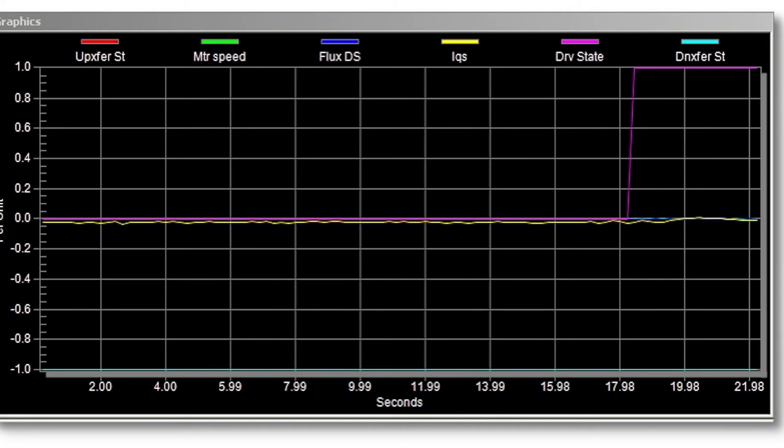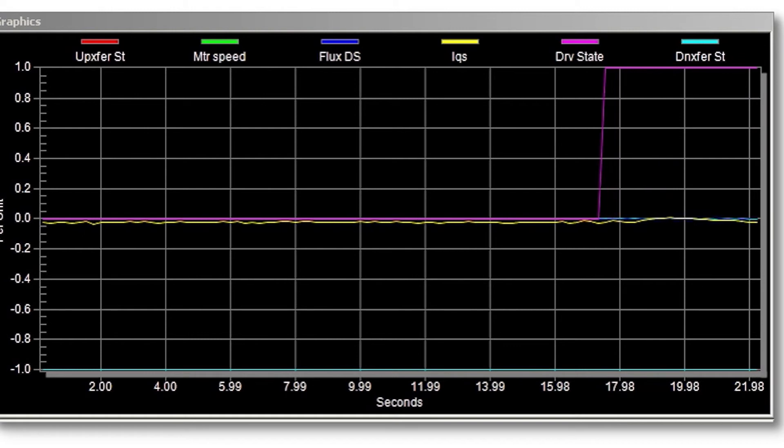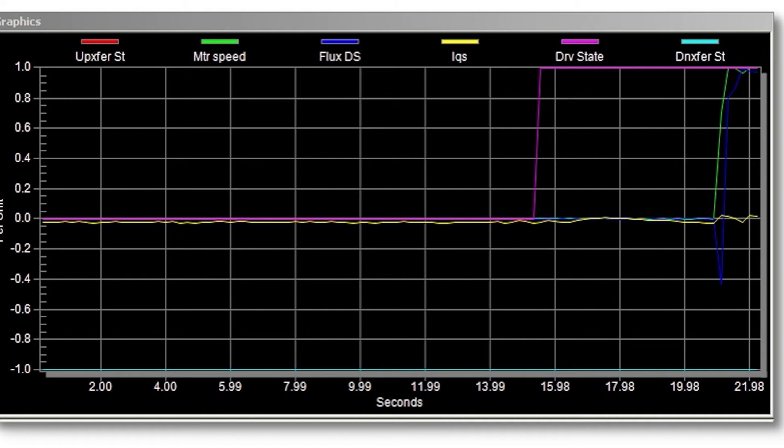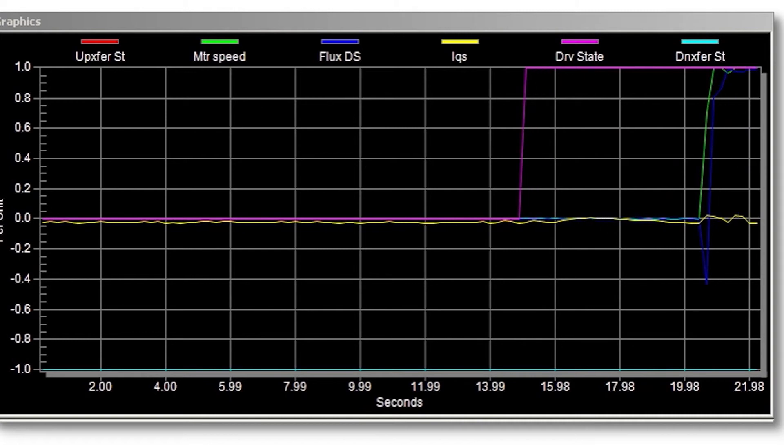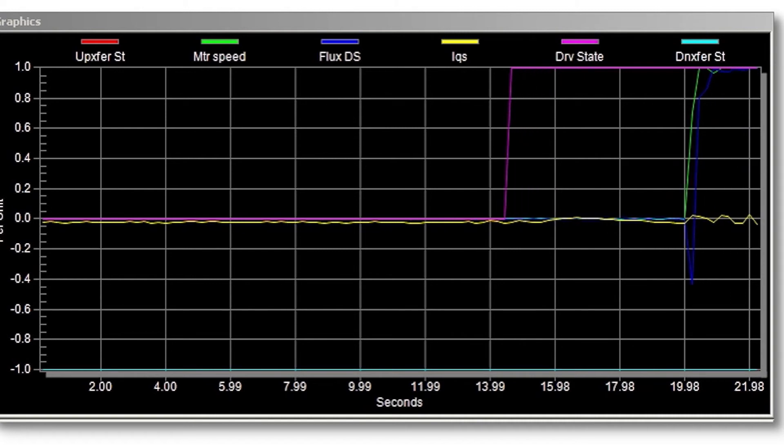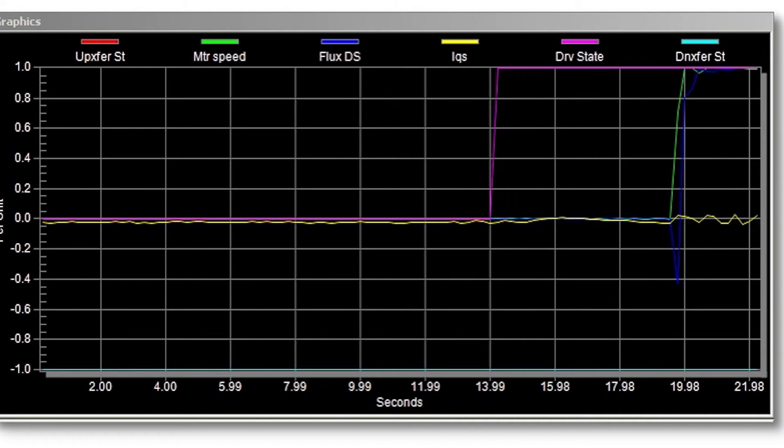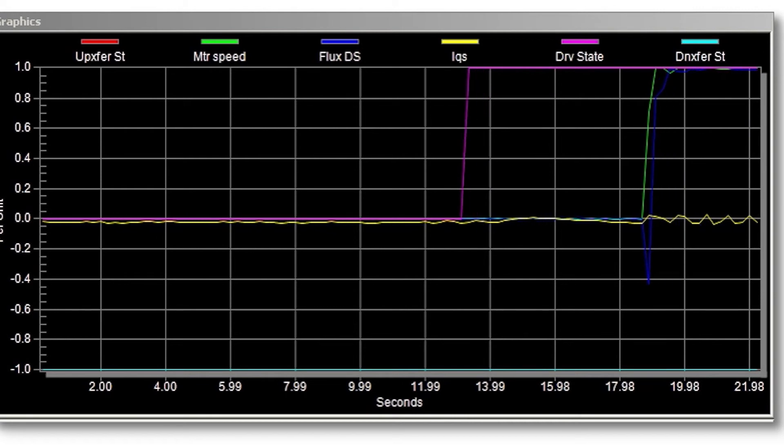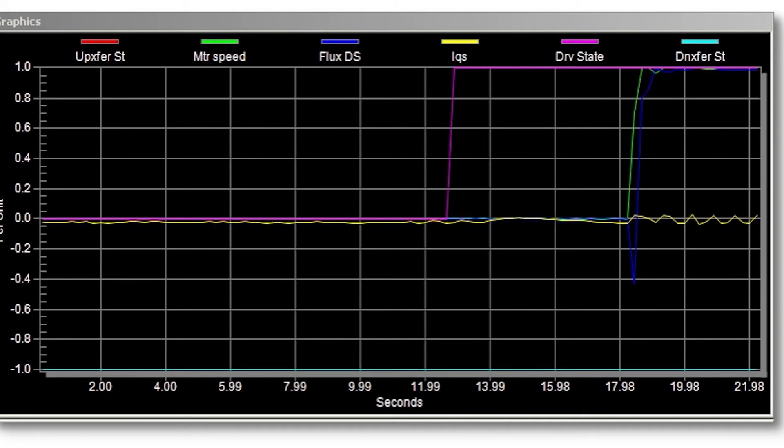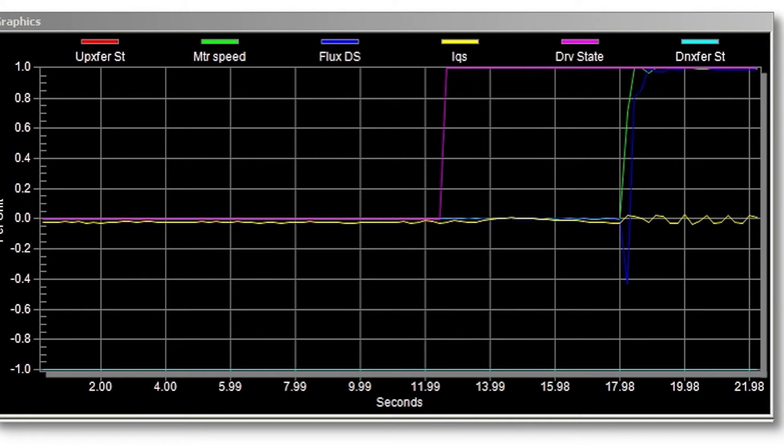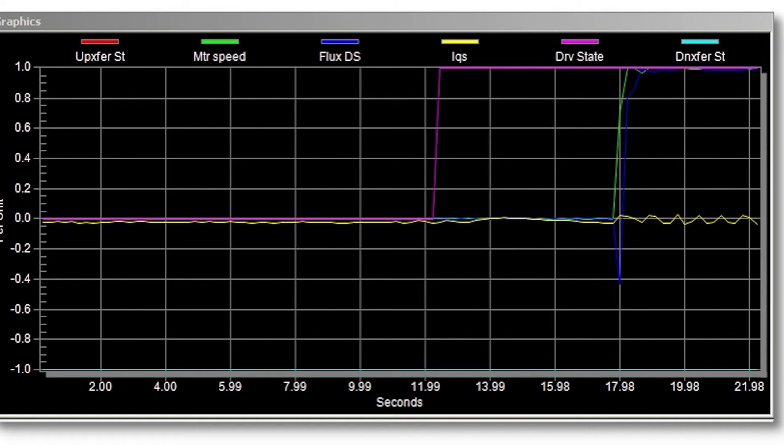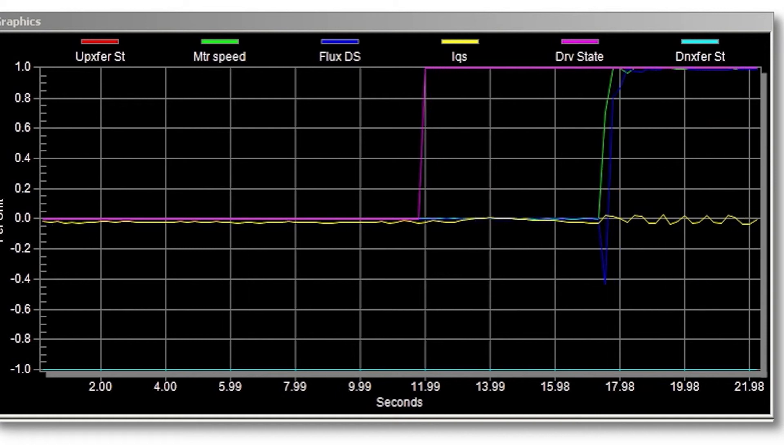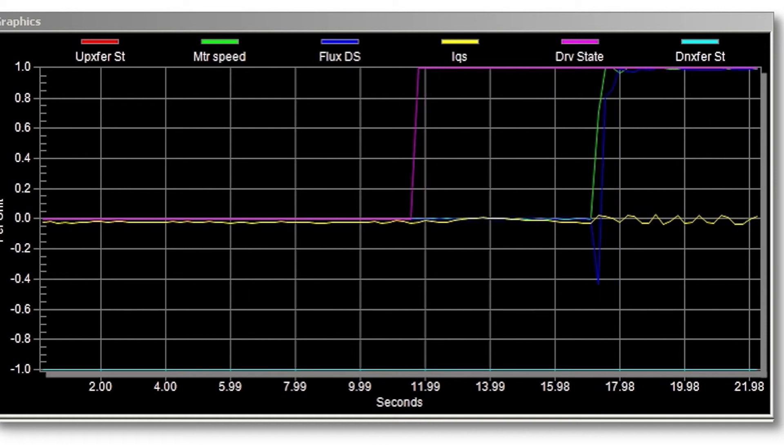The light blue trace represents the down transfer state. In the second stage of the down transfer process, the down transfer request is received and the VFD enters down transfer mode as seen in the purple trace. The VFD output connected to the line and motor achieve frequency and phase lock with line voltage sensed at the VFD output.